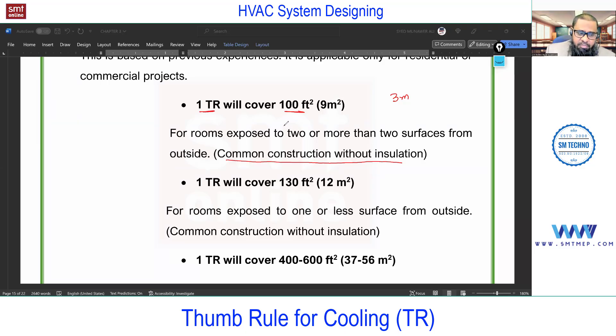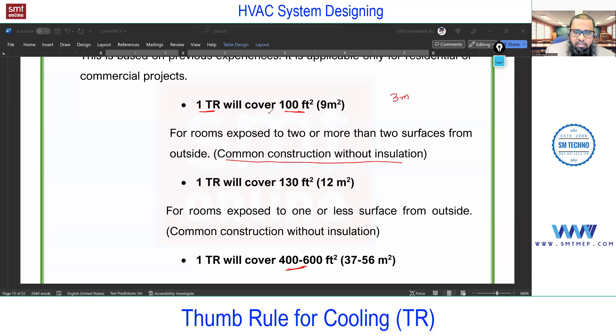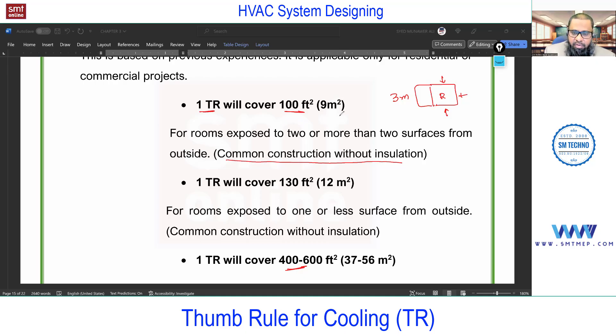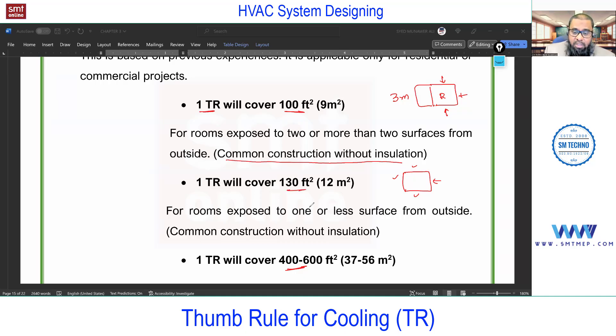Since the market now focuses on energy saving, green building, value engineering, and sustainability, the old 1 TR = 100 sq ft rule represents a very low-efficiency system. It's still used in common practice for small projects in India. For a more exposed room — for example, a room with three sides exposed — 1 ton covers 100 square feet. For a room with only one side exposed, 1 ton can cover up to 130 square feet.